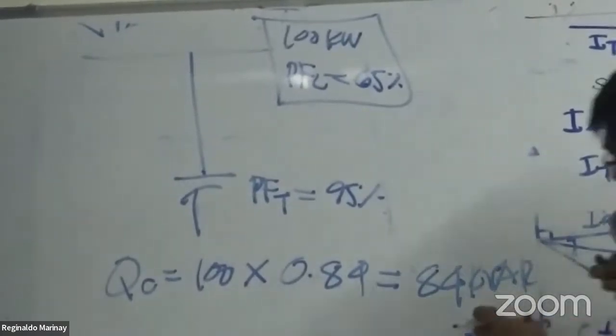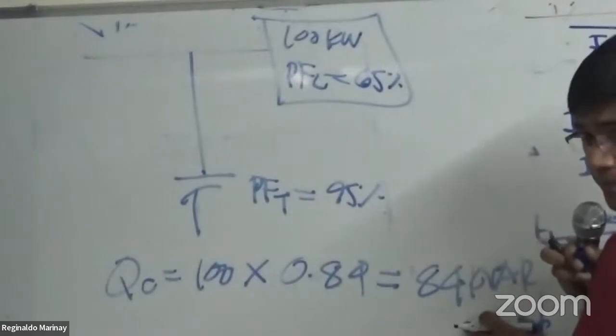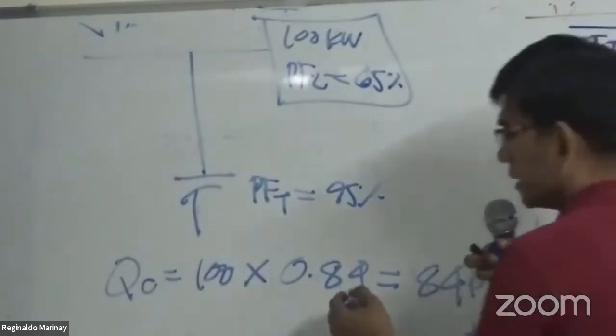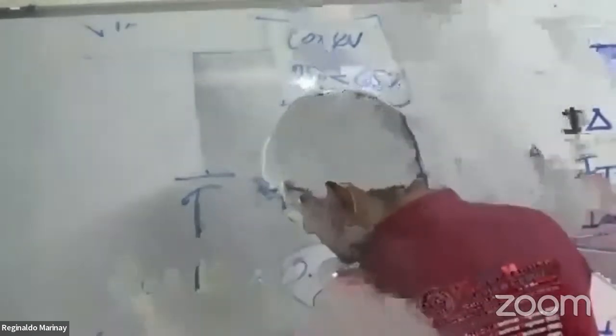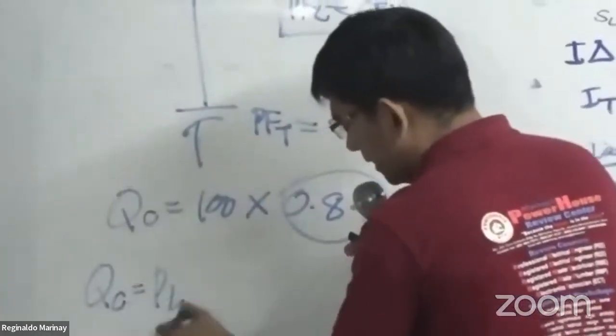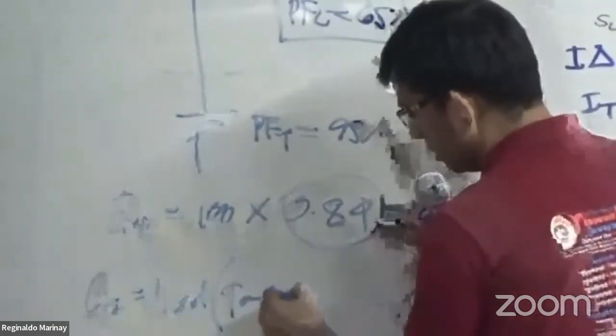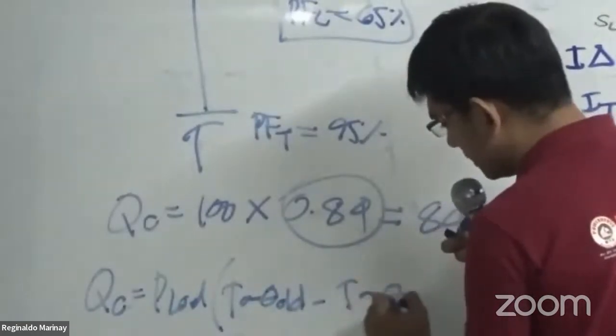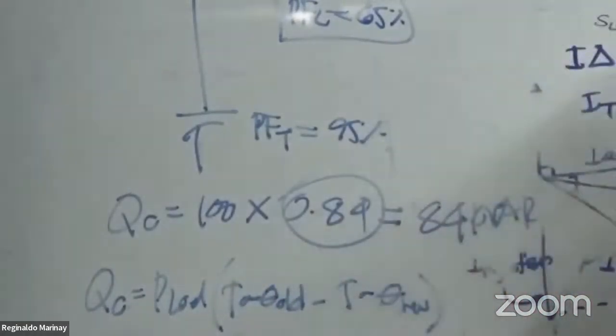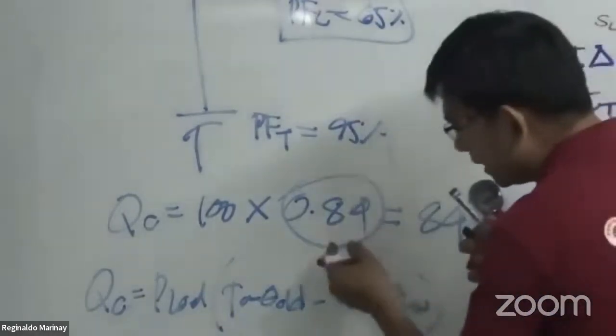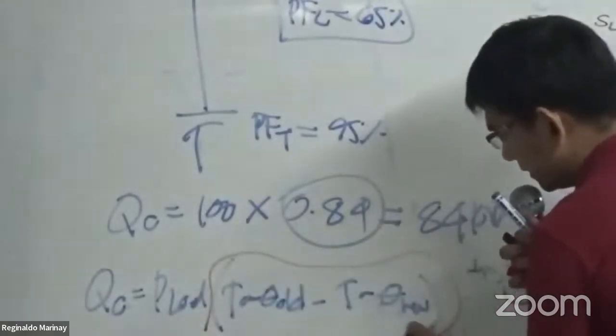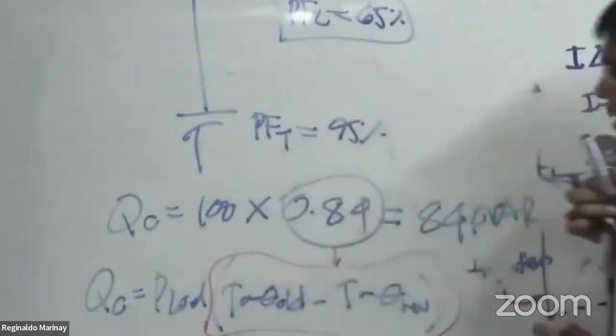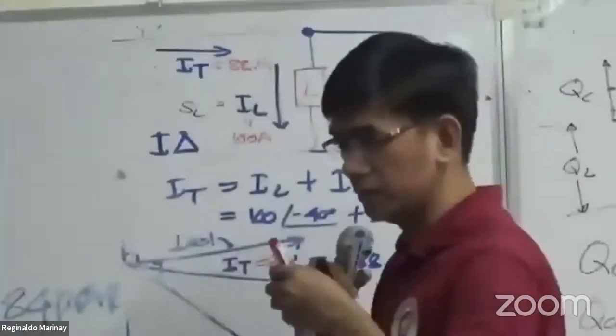So you have your 84 kvar. This 0.84 actually comes from PL, power of the load, times tangent theta old minus tangent theta new. Do you remember this? The 0.84 is that tangent theta old minus tangent theta new. Did you get that? That's why this is a nice, very useful table.